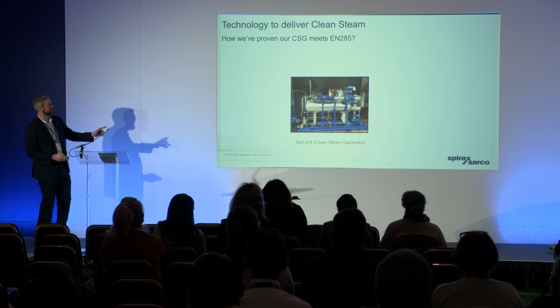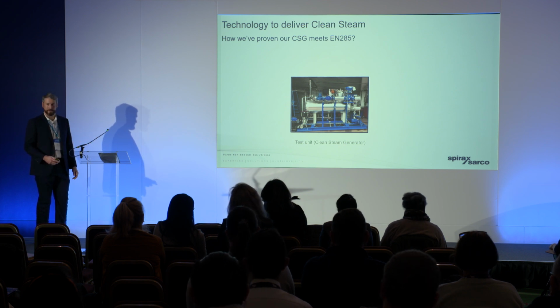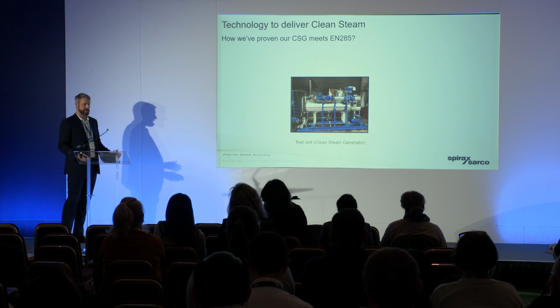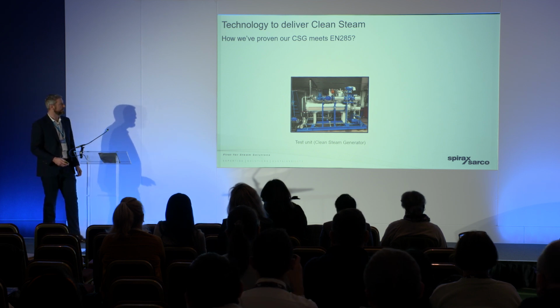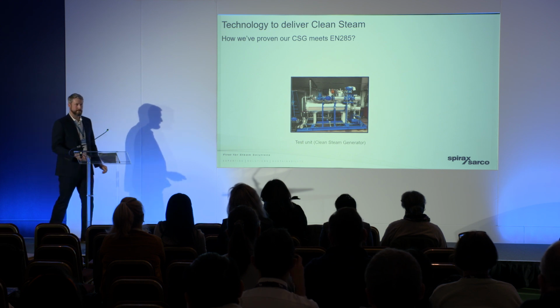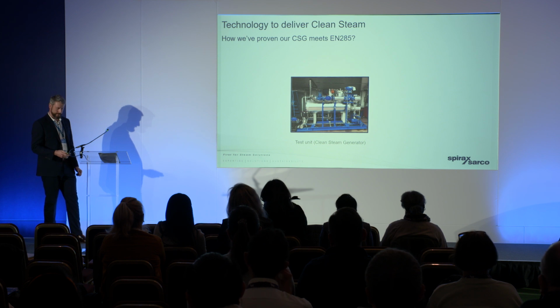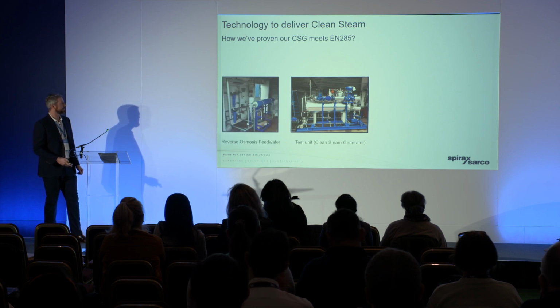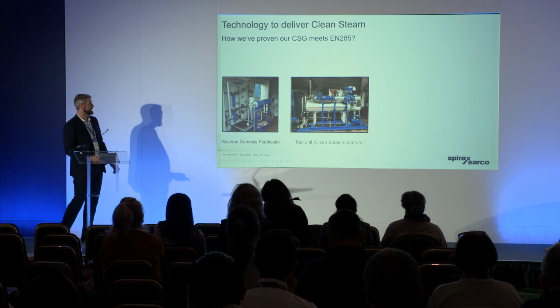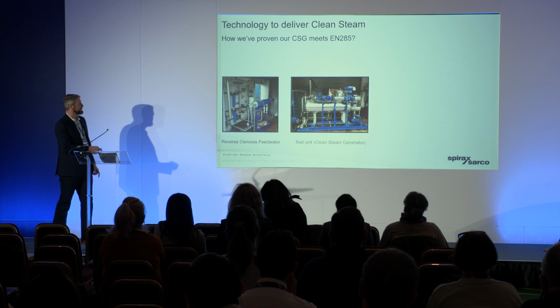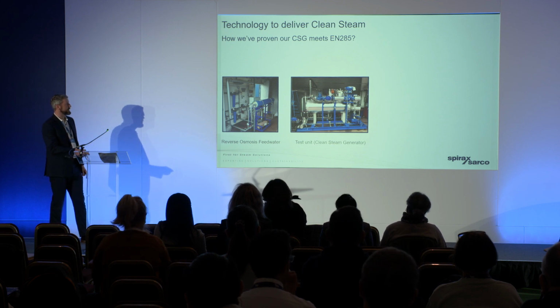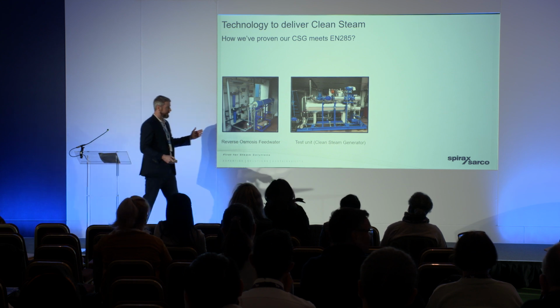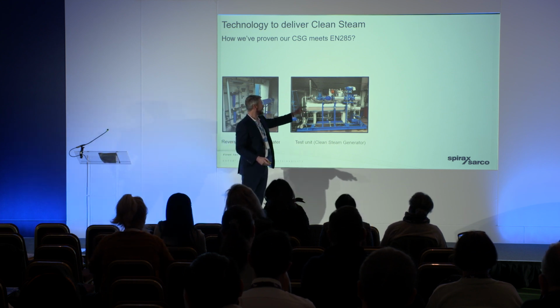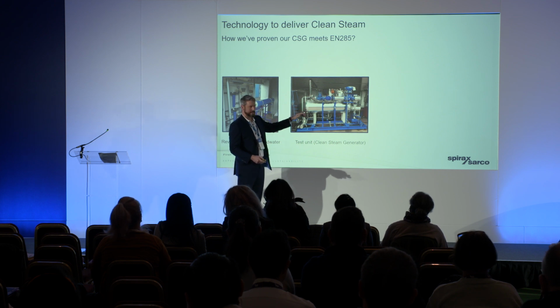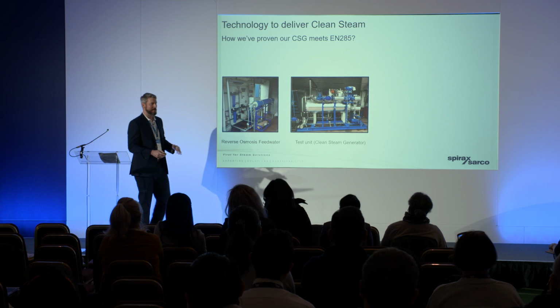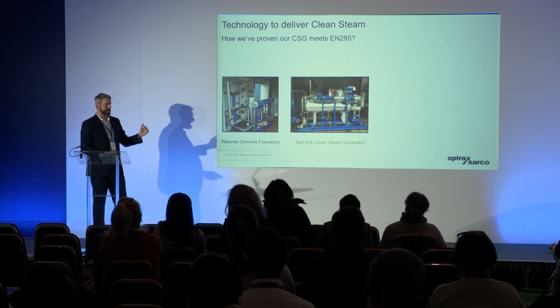So this in the middle here is what we were tasked with designing and developing specifically for sterilization in the healthcare market. I'm going to talk to you a bit about our test setup. It was a multi-million-pound investment. This is our test facility in these images. You can see we have reverse osmosis feed water feeding into our clean steam generator. Our objective here is to make sure that this generates steam for the sterilizer, meeting EN285 compliance all the time, regardless of the loads, however dynamic that system is.